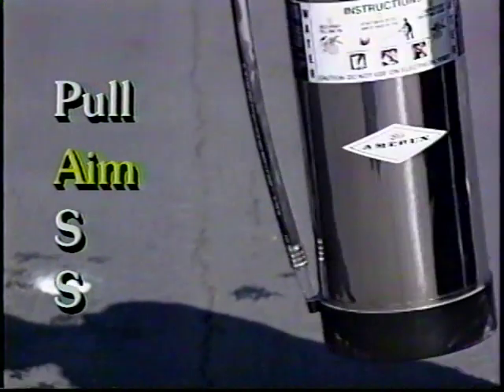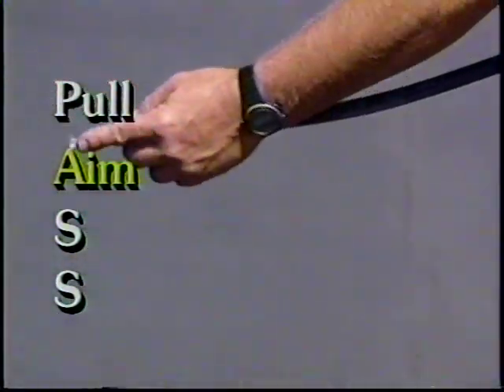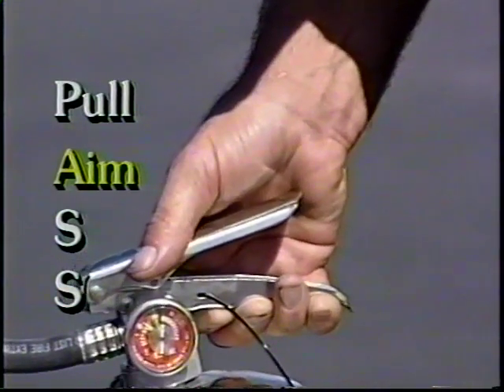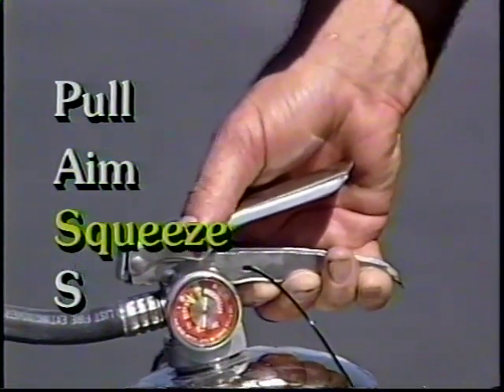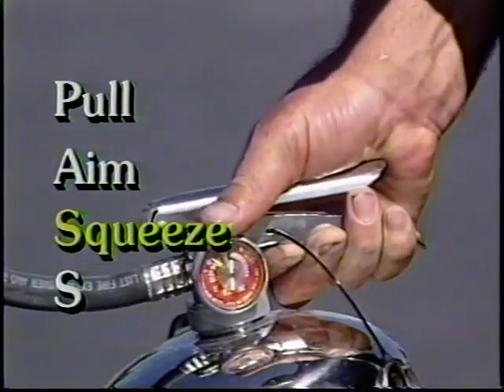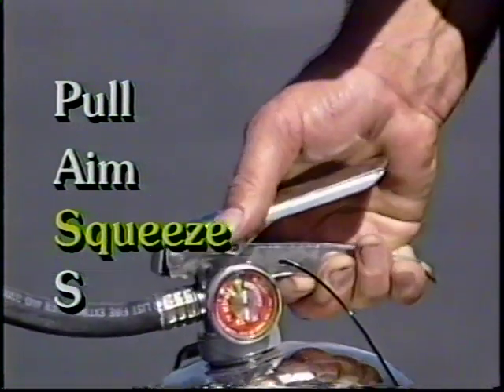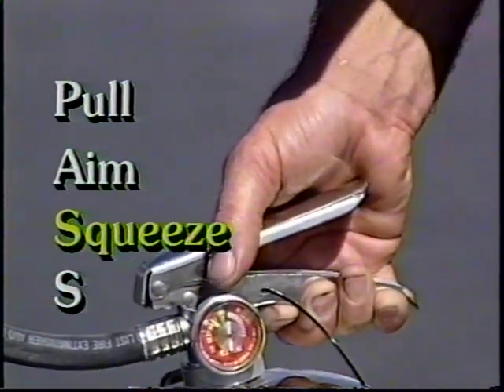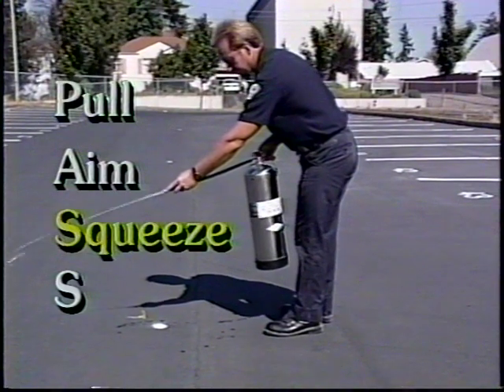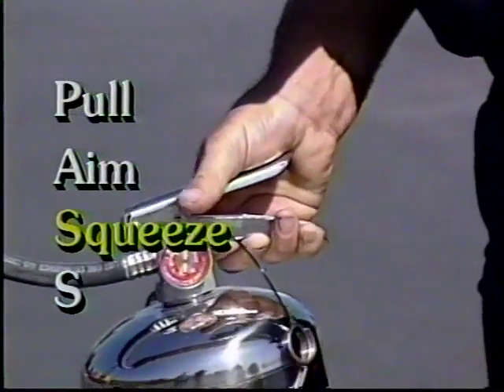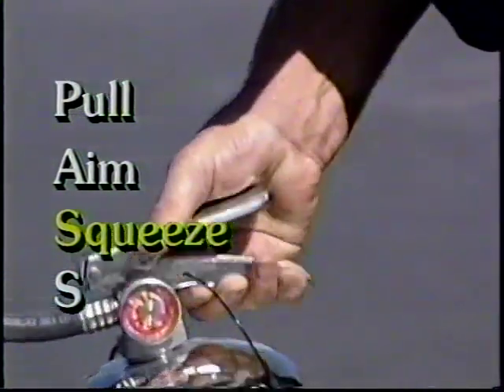If the hose is clipped to the body of the extinguisher, you will have to release it and then point. The S stands for squeeze the handle above the carrying handle to discharge the extinguishing agent. When you release the handle, the discharge will stop. It's best to try a short test while you approach the fire to be sure the extinguisher is working correctly.